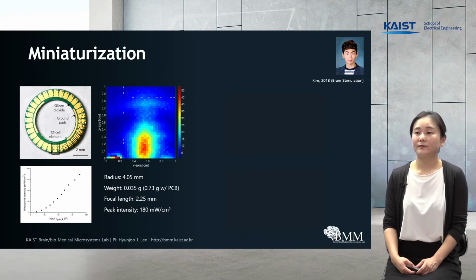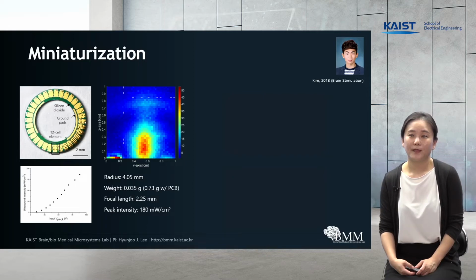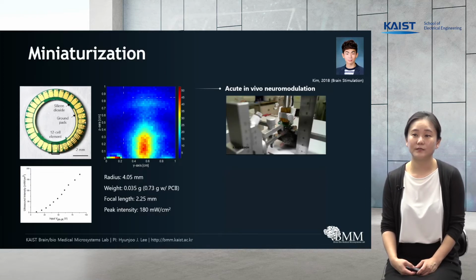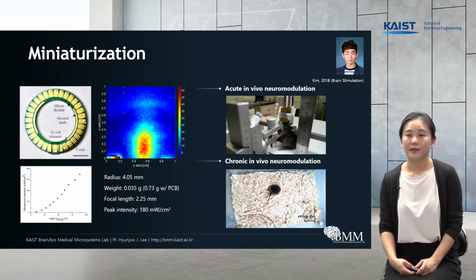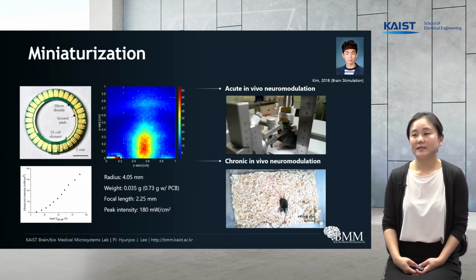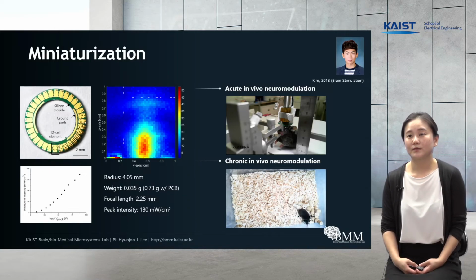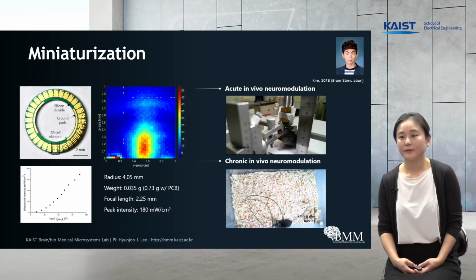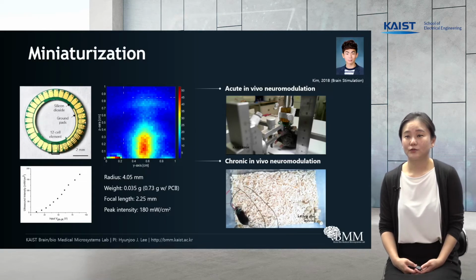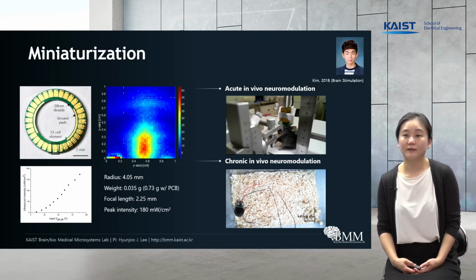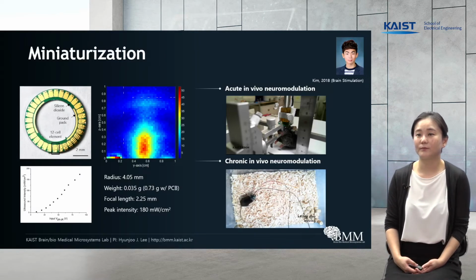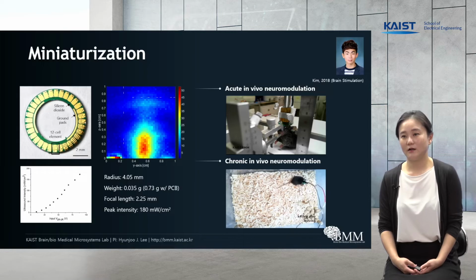Here's a photo of our CMUT ring array with a diameter of 8 mm that weighs only 0.035 gram. As you increase the applied AC voltage, the beam intensity increases. Looking at the beam profile, you see the ultrasound is naturally focused and formed at the middle of the ring. Here's the video of our device delivering ultrasound to the motor cortex through the intact skull. After confirming the successful neuromodulation, we also confirmed stimulating efficacy in the freely moving case, and after fixing our device on the skull, the mouse freely moved around in the cage pretty well.